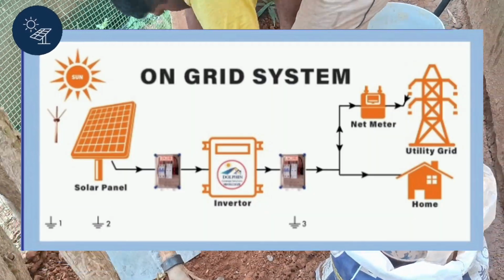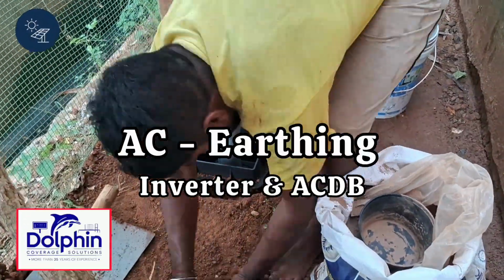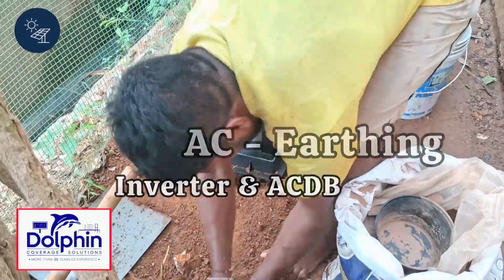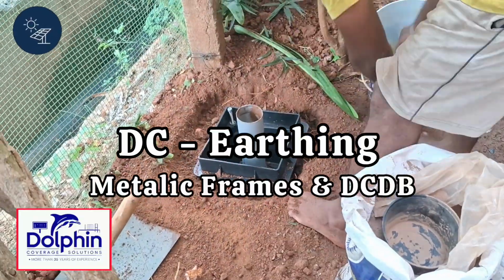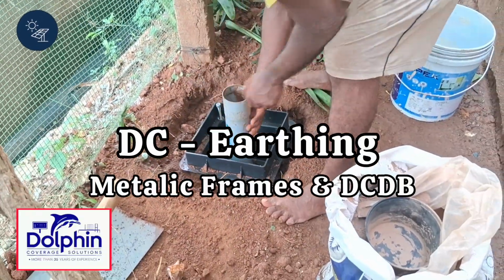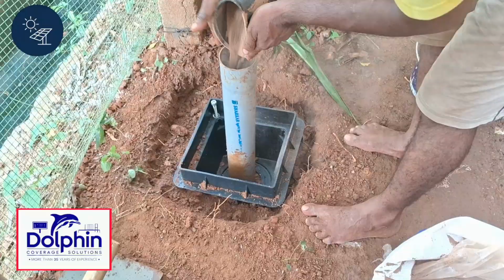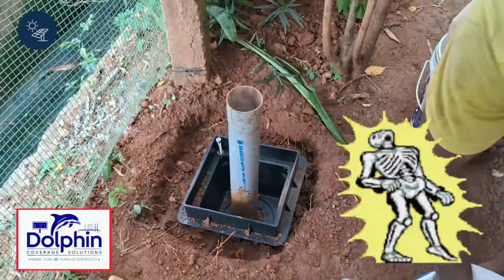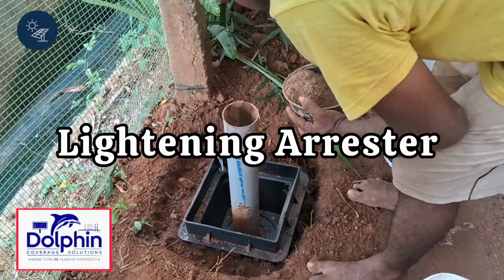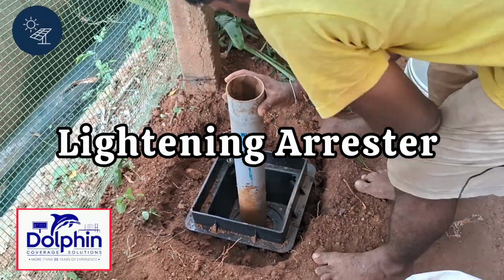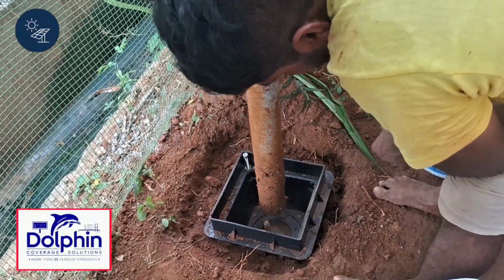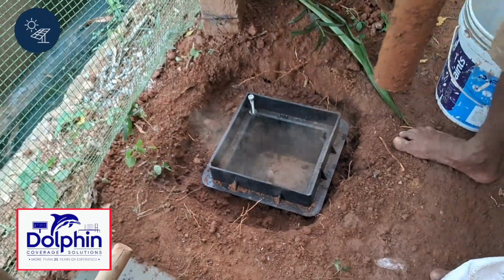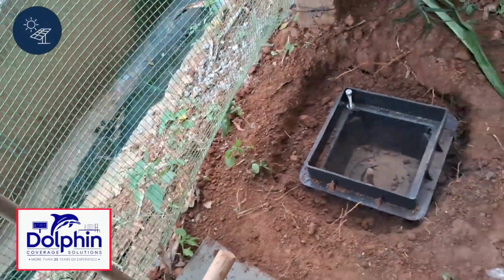Types of earthing. AC earthing for the inverter and AC side components. DC earthing for the metallic frames of the solar panels and mounting structure. This is crucial for preventing electrocution from fault currents in the DC side. Lightning arrestor earthing. A dedicated earthing system for the lightning arrestor is installed. This is essential for protecting the entire system from lightning surges.